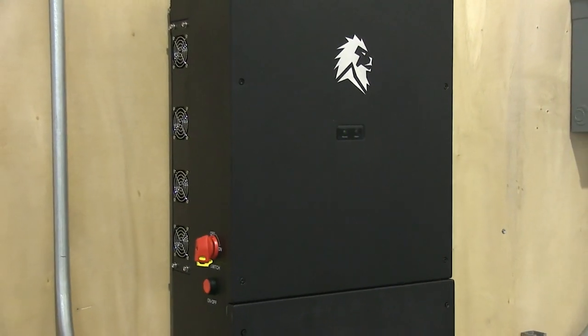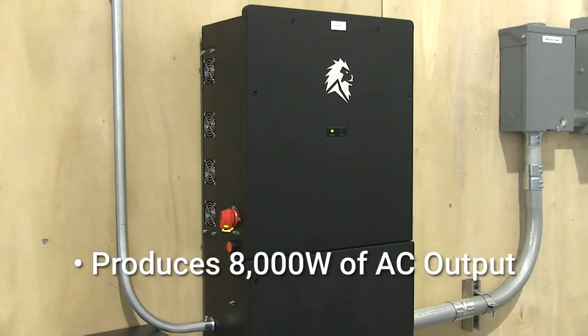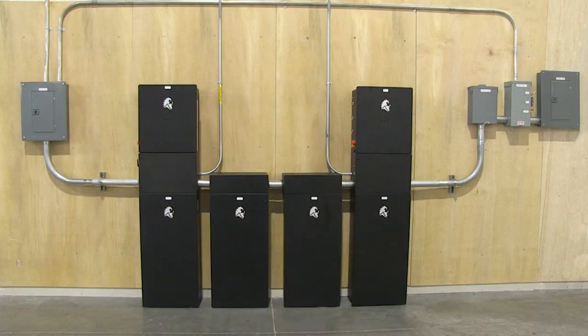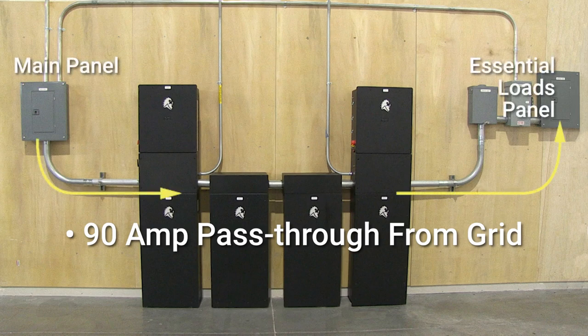The Sanctuary 8k inverter is capable of 8,000 watts continuous AC output — that's 33.3 amps. In addition to the 8,000 watt inverter, it's capable of 90 amp pass-through. This means that you can pull a full 90 amp breaker from your main panel, feed it through the Sanctuary, and provide that 90 amps of energy into your essential load panel, giving you the ability to have a much larger load calculation and cover more loads in your home using a single inverter.